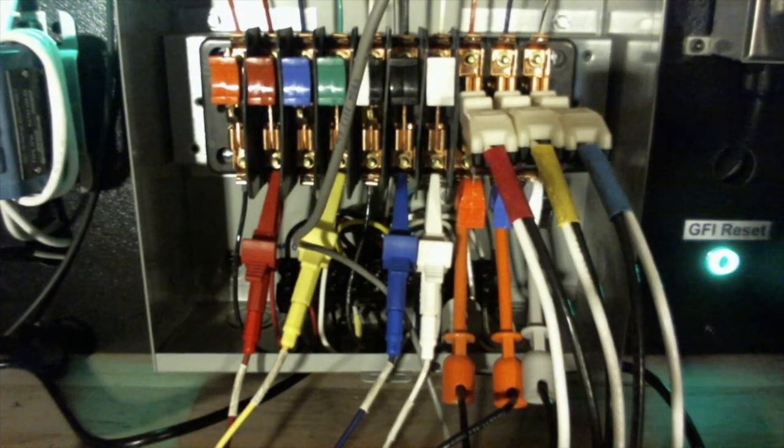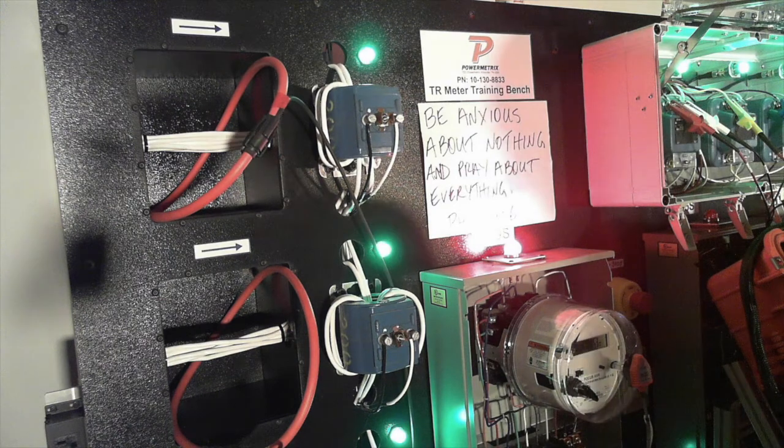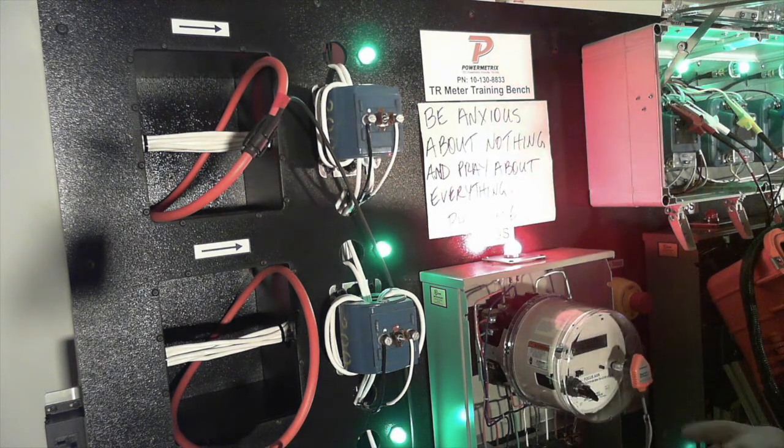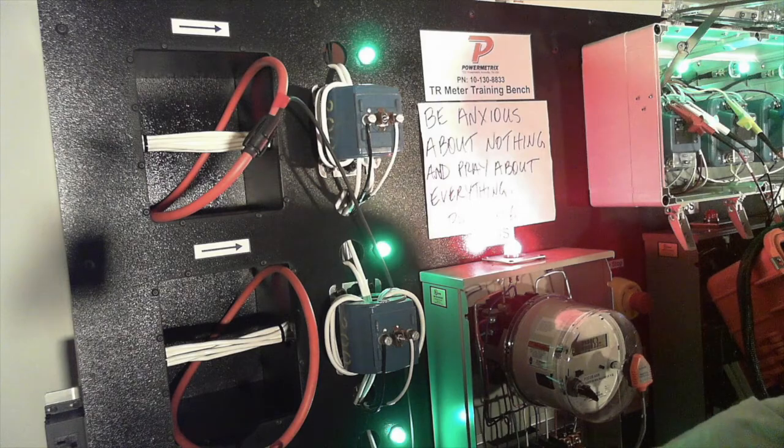You want to be over here? Okay. So what I'm going to do is go onto my CTs here and make a direct connection right here with my voltage connectors. I'm going to take my alligator clips off of here, because if you think about it, my current probes are already telling me the current to the CTs and back. What I need is the voltage, because right now I'm not connected in that circuit out to the CTs and back with my voltage, so I have to get in there with the voltage so that I can use V equals IR.